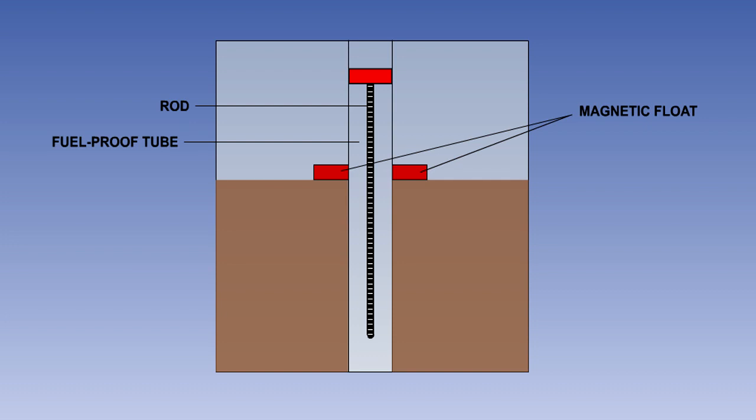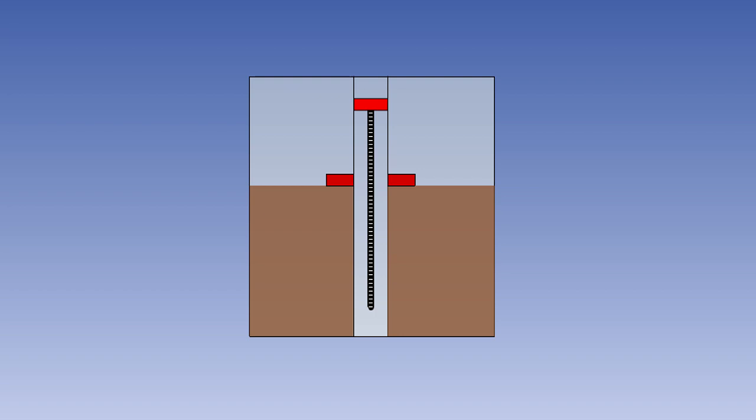Around the tube is a magnet supported on a float. The magnet moves up and down the tube with the fuel. The tip of the rod is also fitted with a magnet. When the rod is lowered through the tube, as the two magnets line up, their fields attract each other and resistance to further movement will be felt.